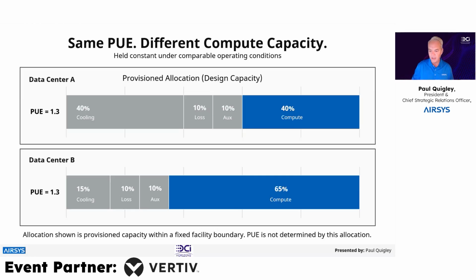You can literally have two facilities side by side with the exact same PUE—both equally efficient in how they use energy overall. But interestingly, these two data centers may not have the same ability to support compute. In this example, one of them allocates more of its provisioned power to cooling and overhead—very typical of data centers that are 3 or 4 years old. The other allocates more toward compute, which is the goal of what we're after here. PUE does not capture this difference.